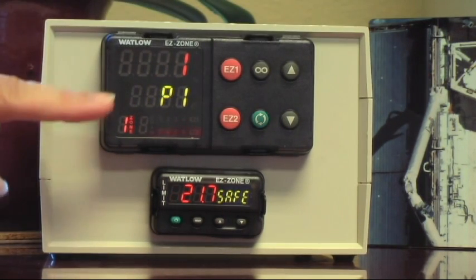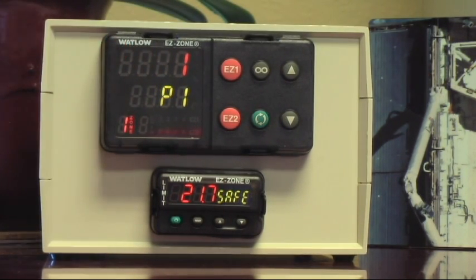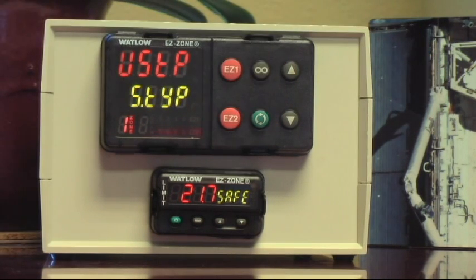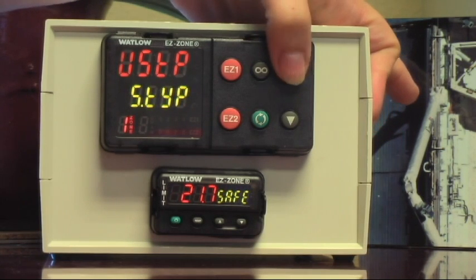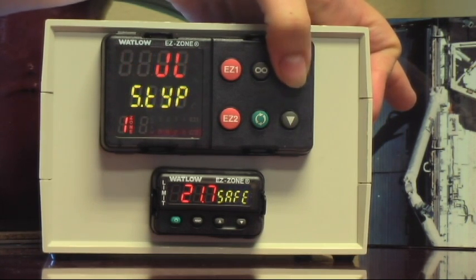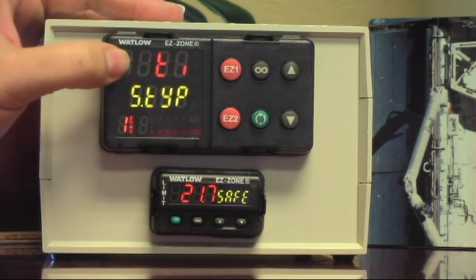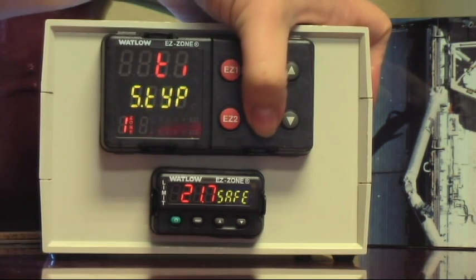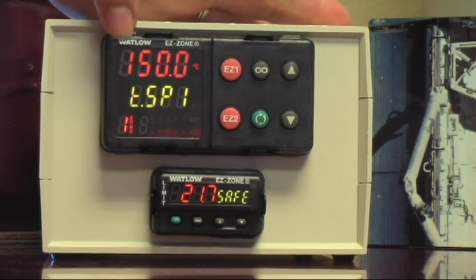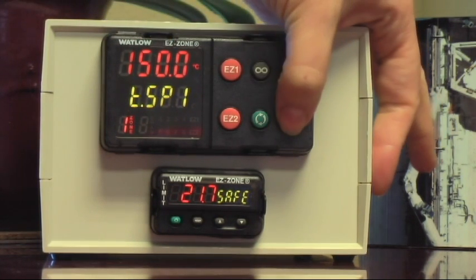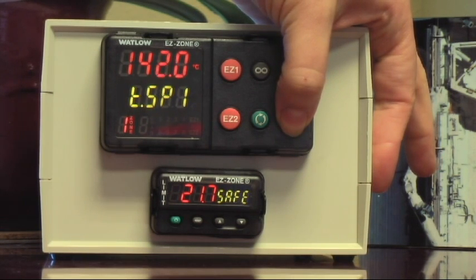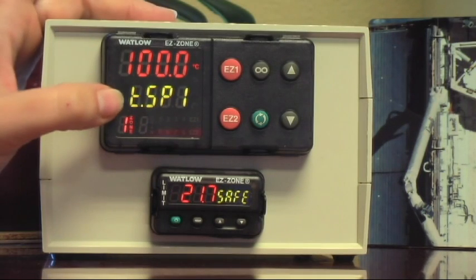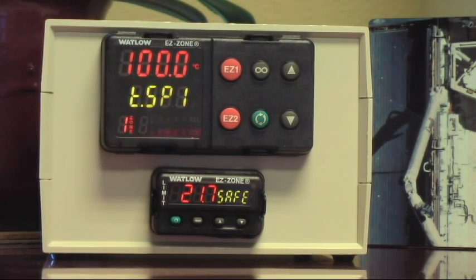Now we're in profile one, step one. Green key again. This is where we select the step type. And the first step type that we want to do is called a timed step. So you'll use your arrow keys to scroll through to the timed step. Then you press the green button again. Now it's set for 150 here, but you said 100. So we're going to use our up and down arrows to select our set point for the timed step. So that's the timed set point one.